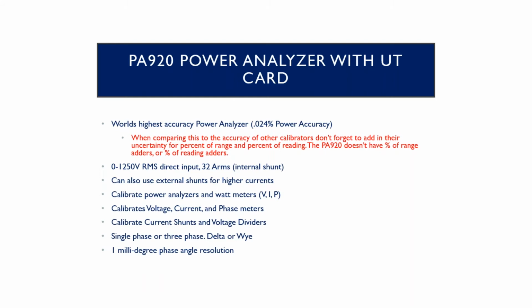Okay. So the UT card is good up to 1250 volts RMS direct input, just banana jacks, and also 32 amps RMS with an internal shunt. You can also use external shunts. So if you have your own favorite shunt, you can plug it in. We work with anything that outputs 0 to 5 or 0 to 15 volts or anything in between. You just put in the scaling factors and we'll read out directly in amps.